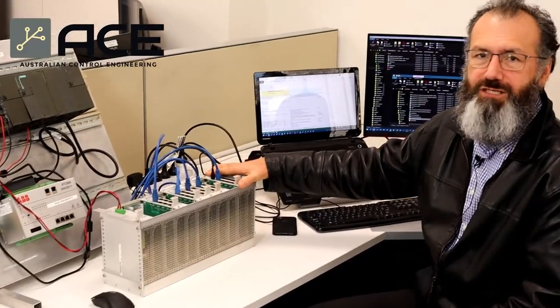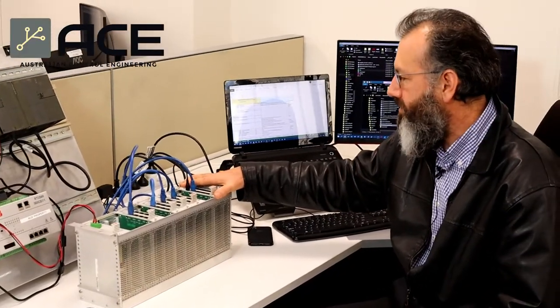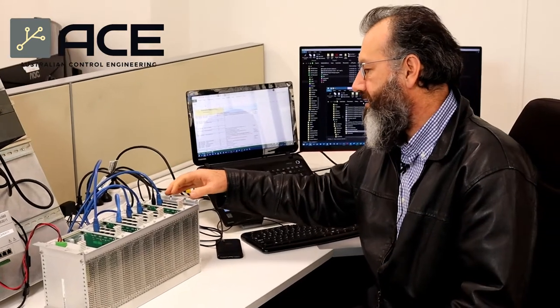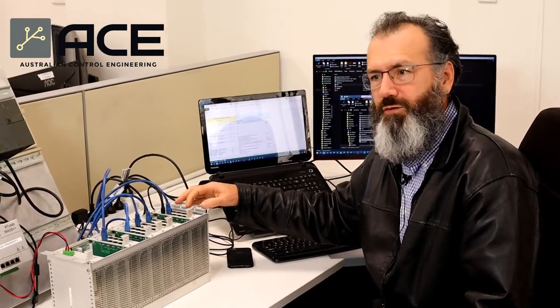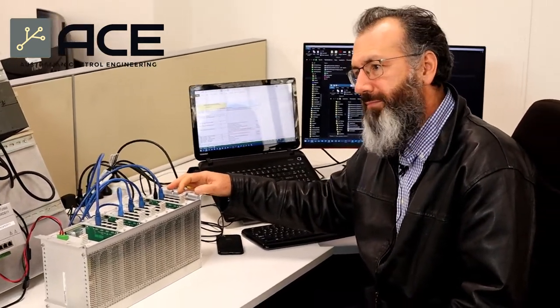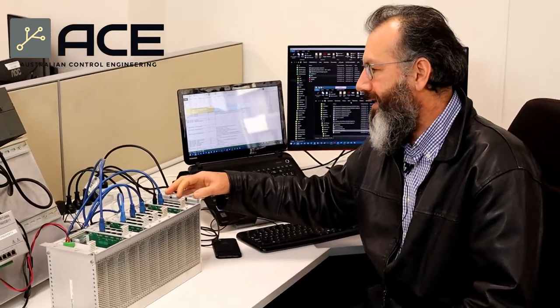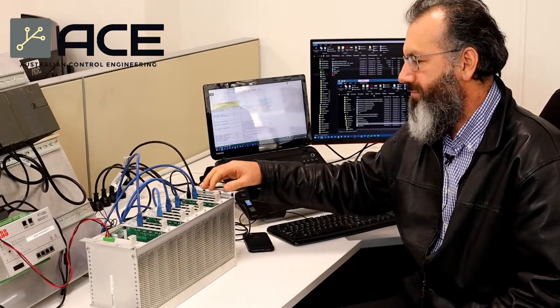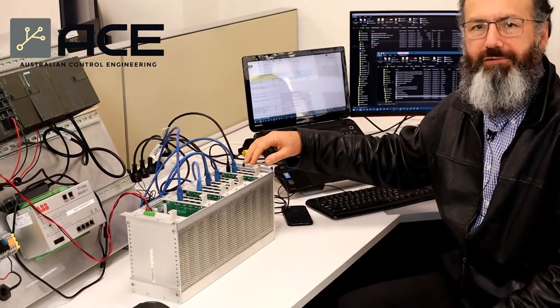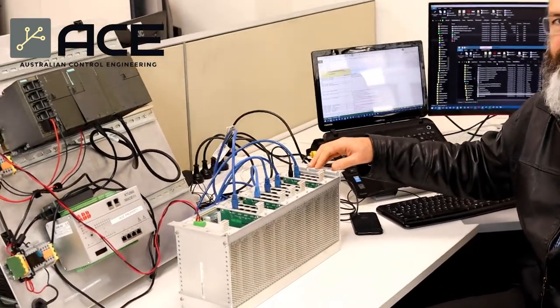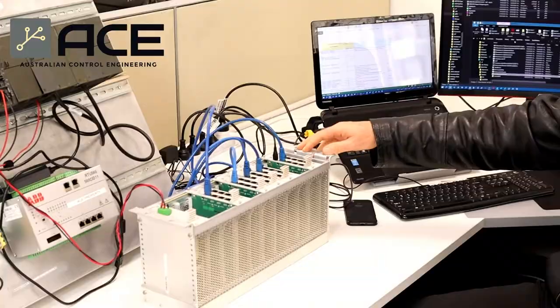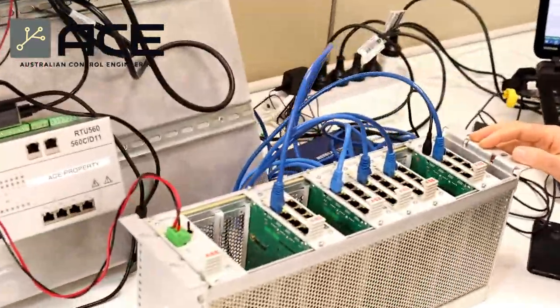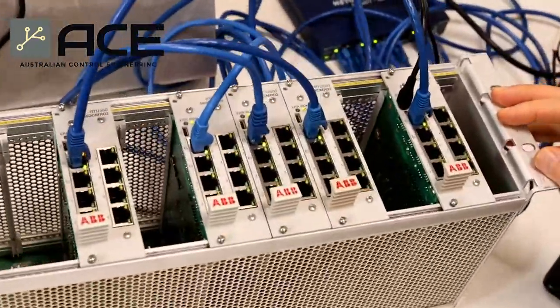One of the issues we encountered is that in this rack, we have a dip switch for setting the rack number. But in this case, this particular model ignores the rack number altogether, so we had to modify our configuration from rack 1 to rack 0.